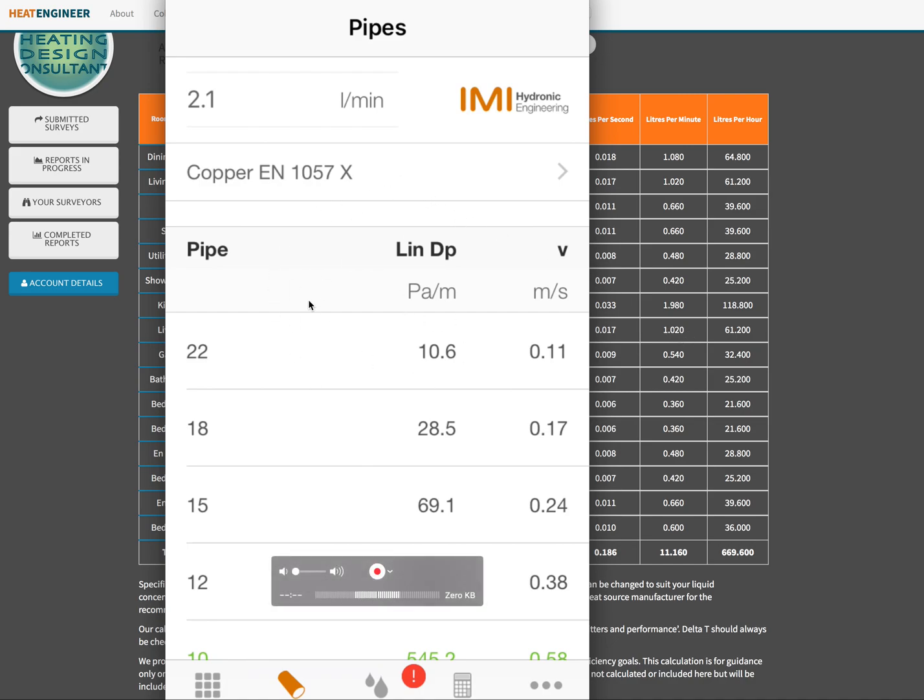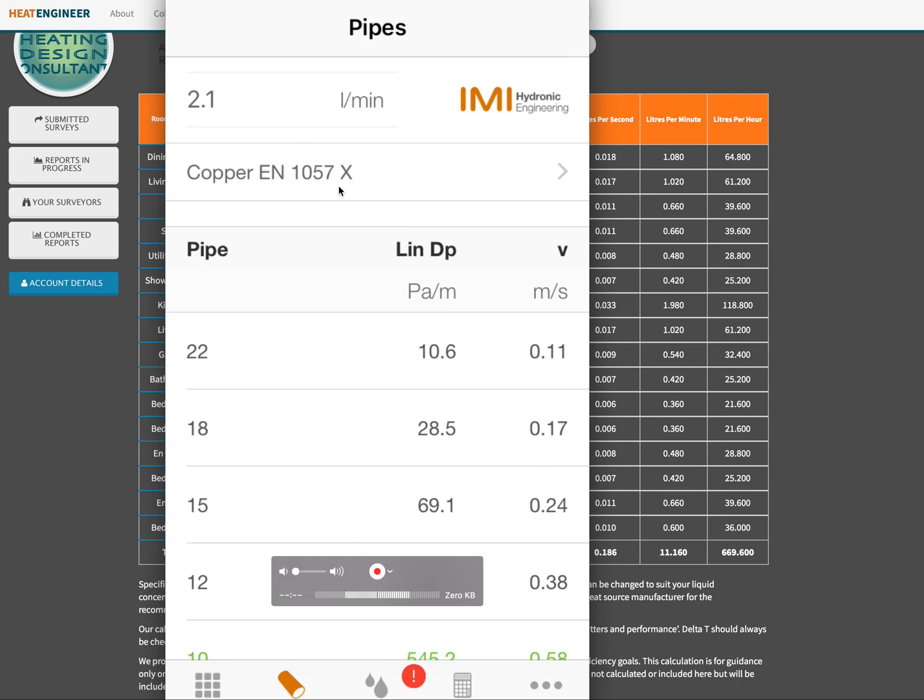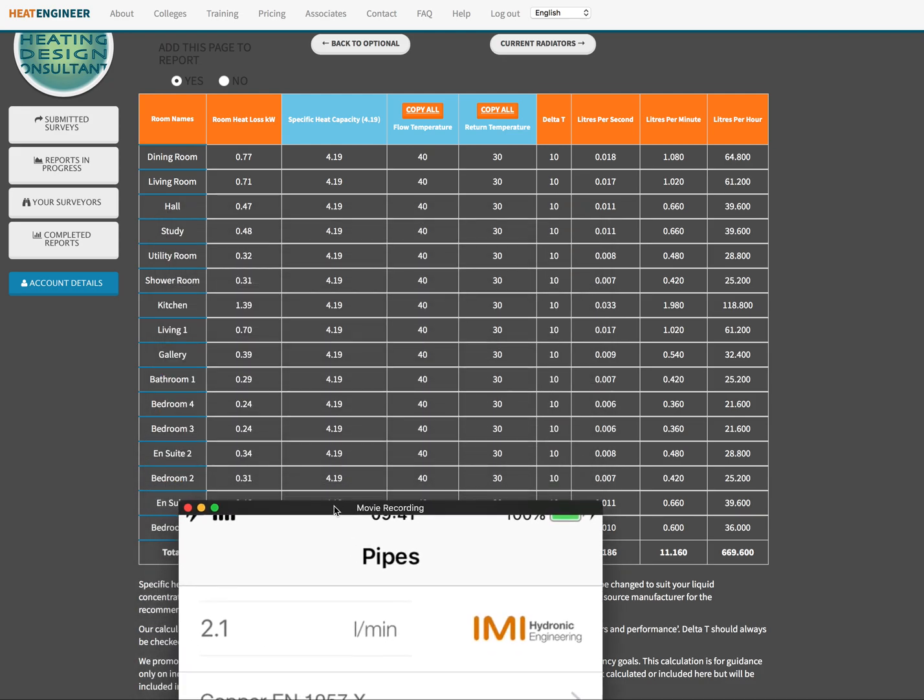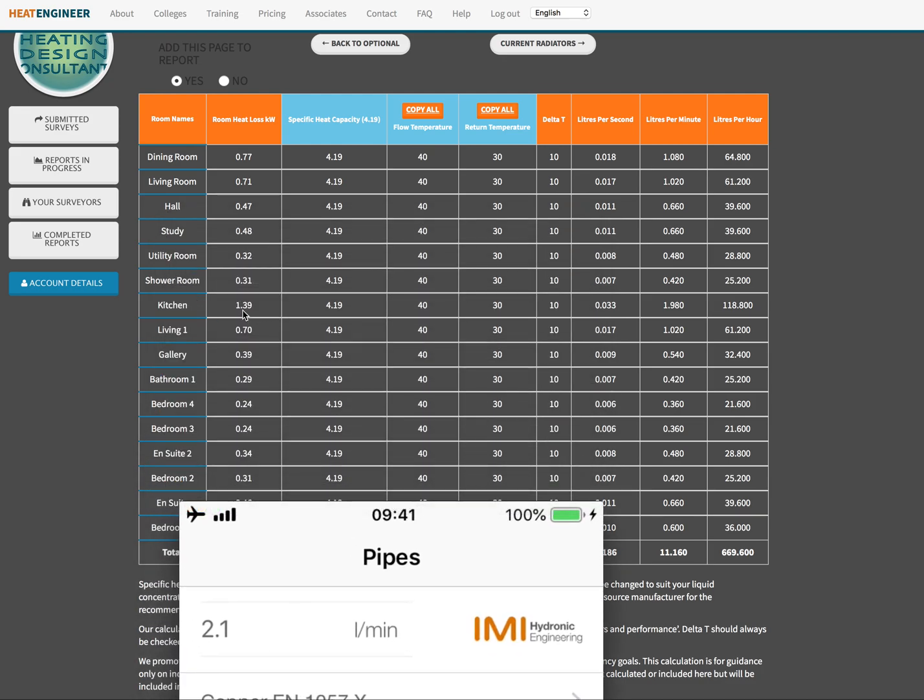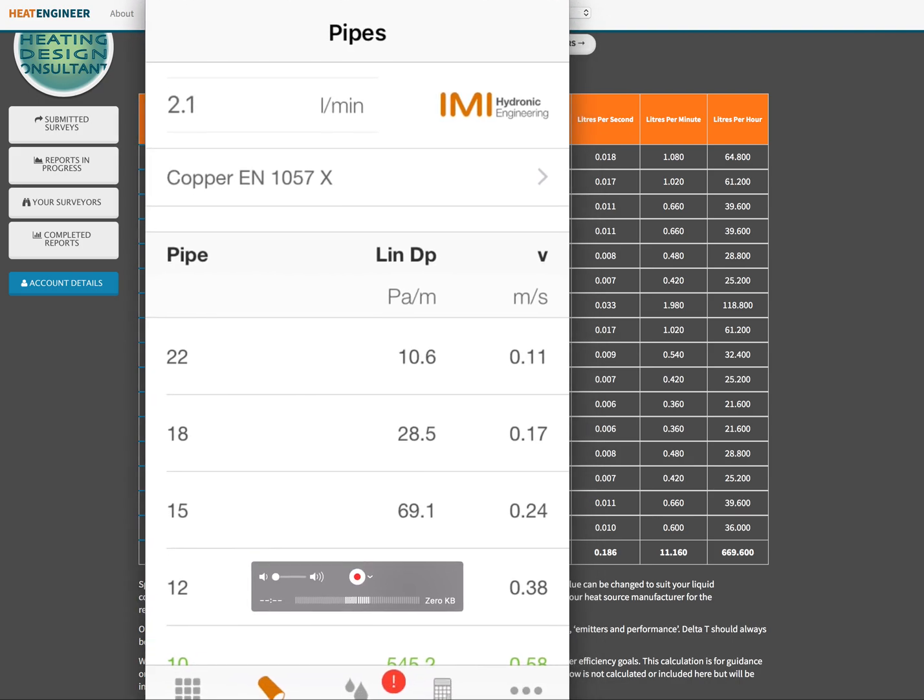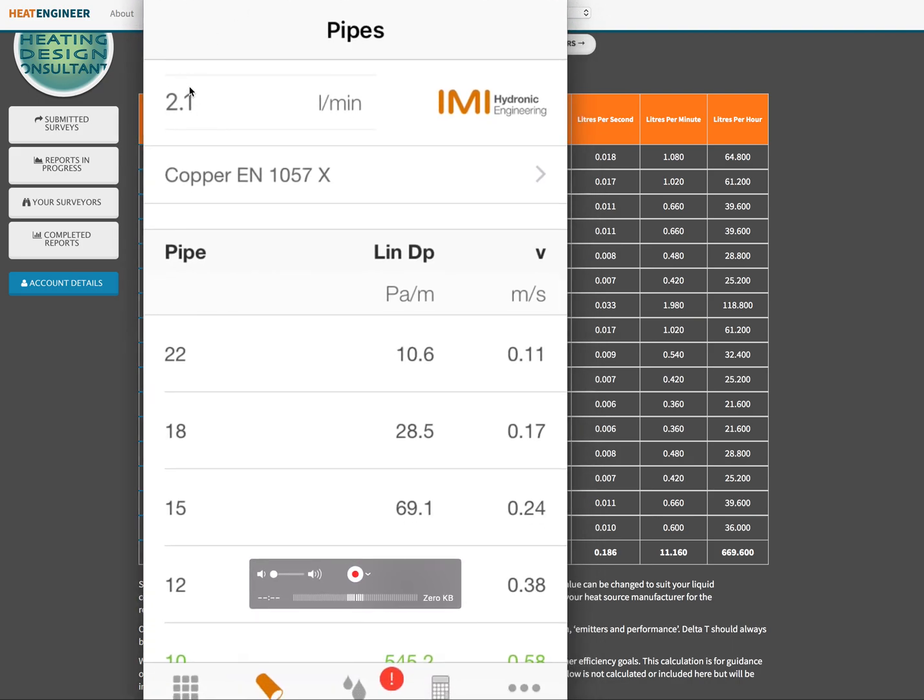This particular app will help you decide on what size of pipe work to do so you're within those realms of the CIBSE guidance and you won't make the mistakes. So looking at this we've just chosen copper table X copper which is what most people would use. We imagine this is radiators for argument's sake that are running through. We've got this set to liters per minute but you can set this to liters per hour or you can set it to liters per second. Now if we remember we were looking at the kitchen and the kitchen was 1.39 kilowatts. We've got this set to liters per minute as you can see here, so 1.39 kilowatts equates to 1.98 liters per minute.